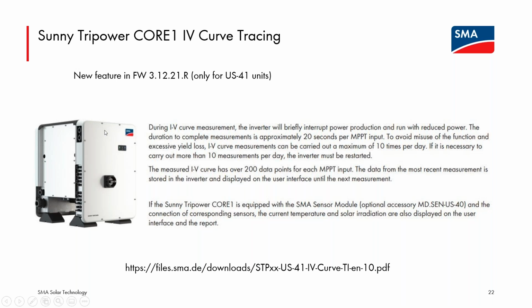3.12.21, and this is firmware only for the US-41 units. But with this firmware installed, you now have the ability to log into the user interface of the CORE1 and ask the inverter to perform an IV curve trace on all of its 6 input tracking channels. You do this while the inverter is in operation. You start this request, and then the inverter sequentially takes each of the 6 tracking channels out of operation, performs that IV curve trace from VOC down to short circuit current, puts that channel back into operation, moves to the next one, does the same curve trace, and when the tracking is done, presents that in the user interface. This takes roughly 20 seconds per tracking channel, so about 2 minutes to perform that IV curve trace.